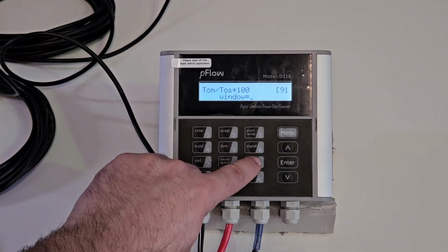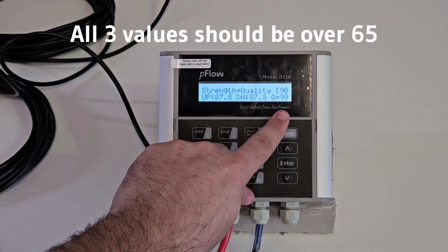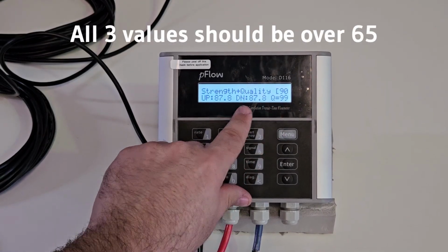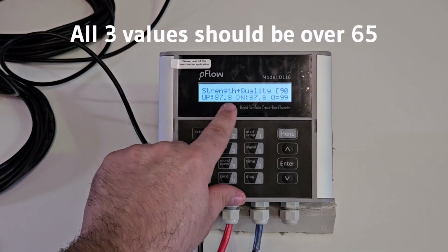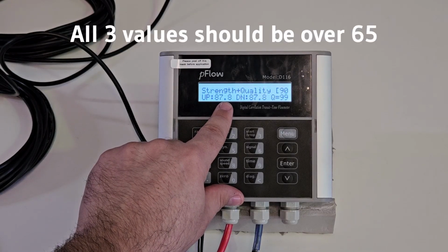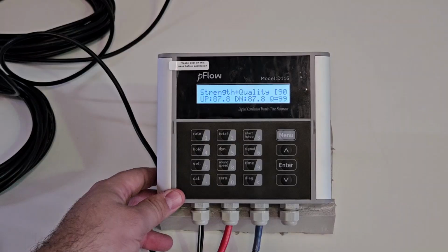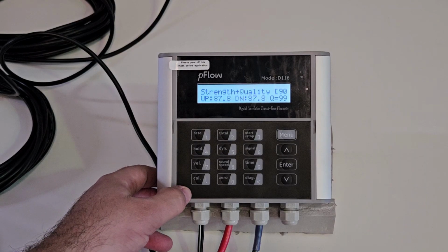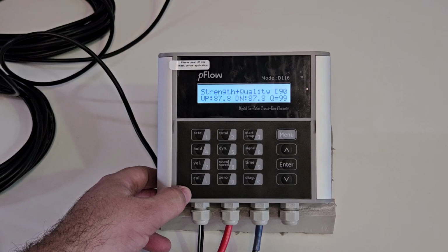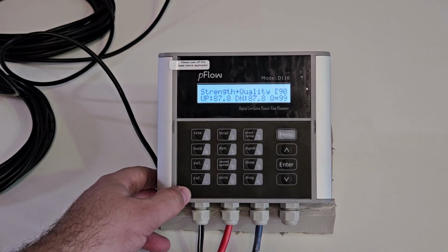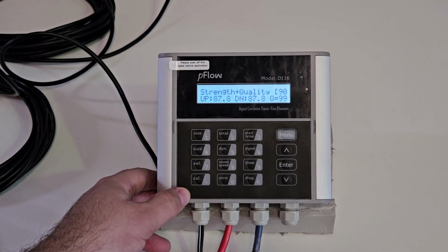Next, check menu 90 to display signal. You want signal to be as high as possible. Check these three values displayed. In general, these values should be 65 or higher for normal operation. If any of these checks are out of range, it can indicate a problem with the application or installation. Please recheck parameters and installation, or check through the installation guide and manual to troubleshoot. Maybe there is a parameter incorrectly set or a problem like not enough straight pipe length causing flow turbulence, aeration, or too much suspended solids.